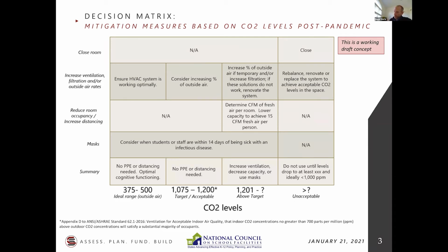Okay. And 700, tell me where that number evolves from. That has to do with how many air changes you can provide. Again, if you're in a typical classroom where you have 15 to 30 people in there, if you're providing 4 air changes, something along those lines, you'll be looking at concentrations of about 700 to 800 parts per million.